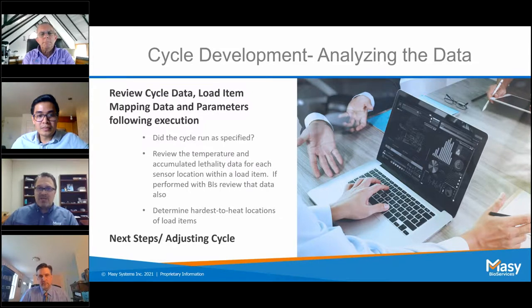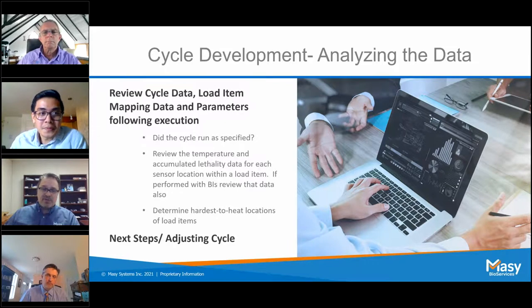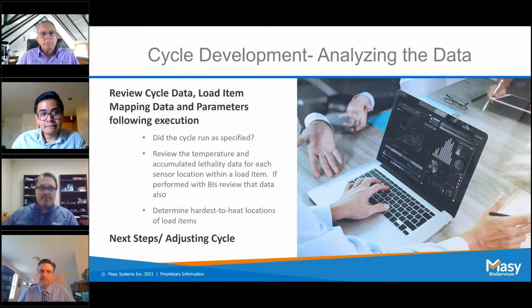And then also look at that data and use it to determine where those hardest to heat locations are. You might have to run several cycles to actually get that figured out. The idea is really that we want to have a robust qualification. So make sure you're comfortable that you've collected enough data with those developmental runs, and then you'll have a very good idea of where you want to put your thermocouples and your BIs when you're doing your actual PQ runs. Use that information as well to determine if you have to adjust your sterilization times. You might decide to increase your exposure to have a very comfortable margin of achieving the lethality that you want.